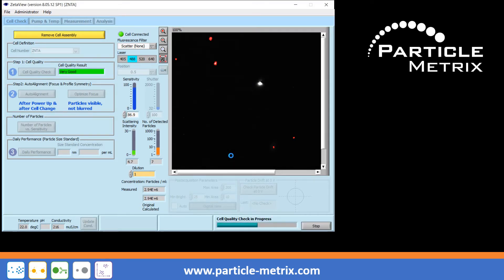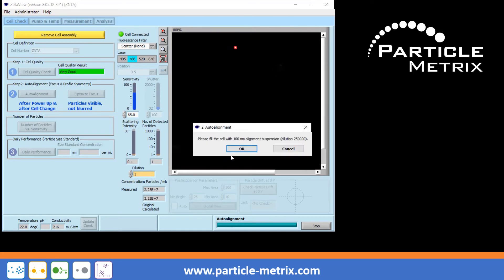After rinsing the instrument, the cell quality check can be performed. After the cell quality check has passed successfully, the auto-alignment function is started automatically.